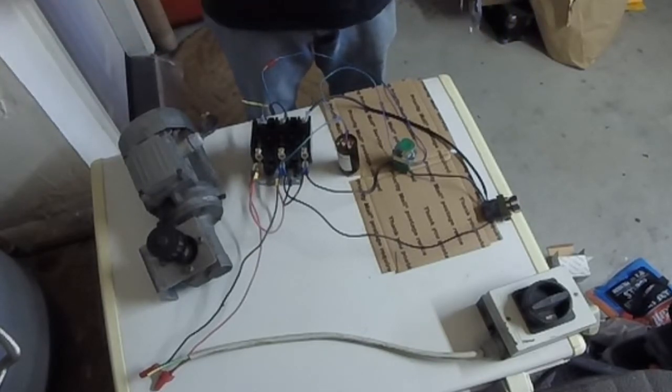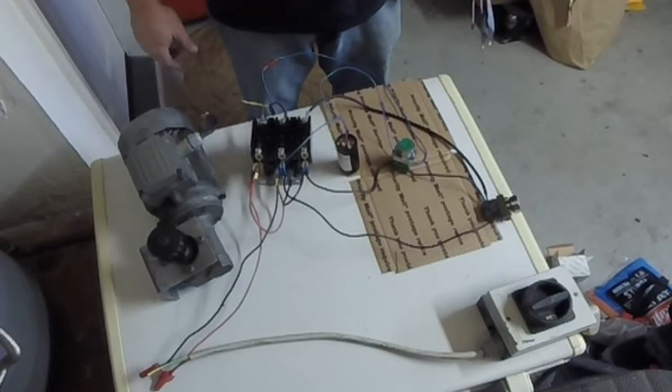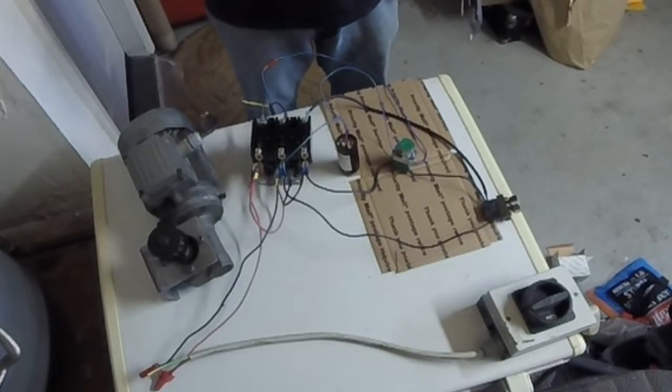10 microfarads one way or the other really isn't going to be all that big a difference. You go 100 microfarads one way or the other, that can be a little bit bigger of a difference. But if you're going to err to the plus side, it just makes the motor fire off faster within reason, of course.